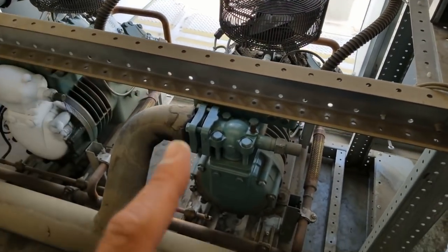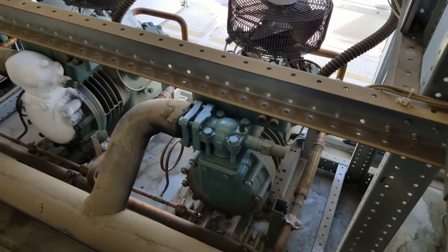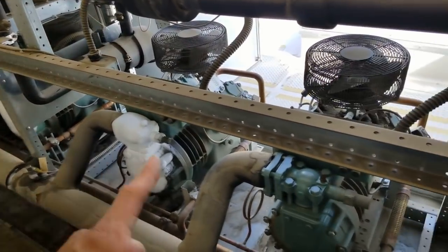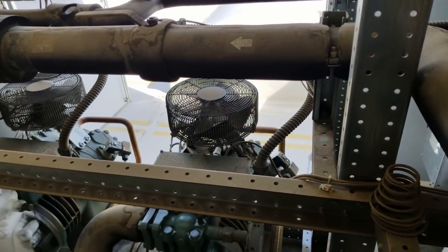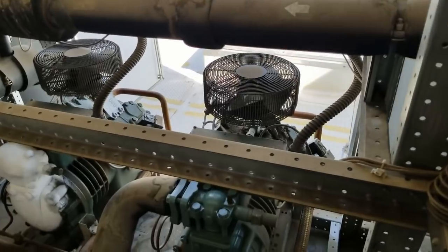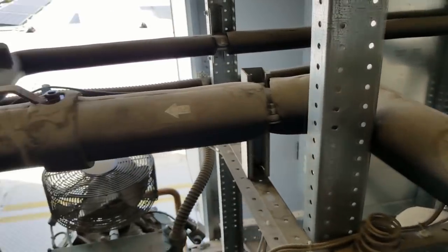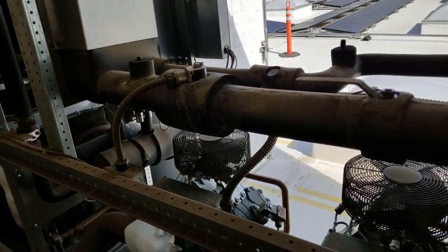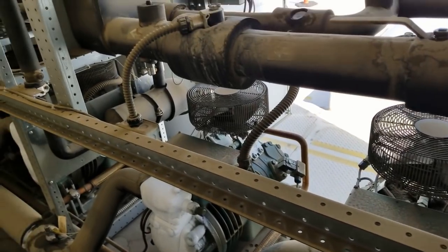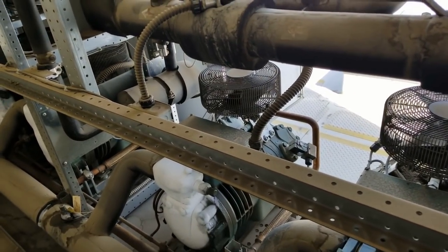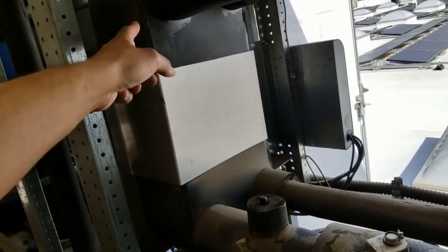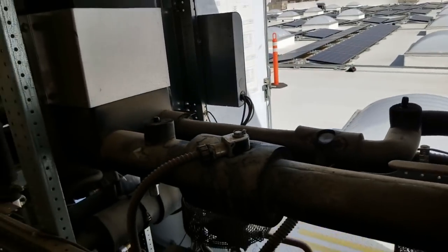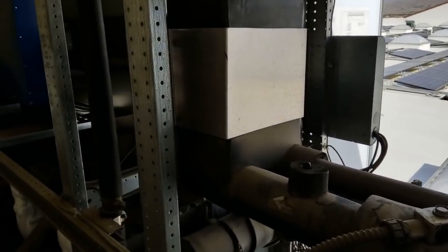This one here is like a regular refrigeration rack where it's a common suction line with 4 compressors, a common discharge line with 4 compressors, and it all goes to one. There's no receiver. Well, actually, I take that back. There is a receiver, and that's underneath the evap tower outside. You got your subcooling here for your refrigeration. Let me see what else we got over here.